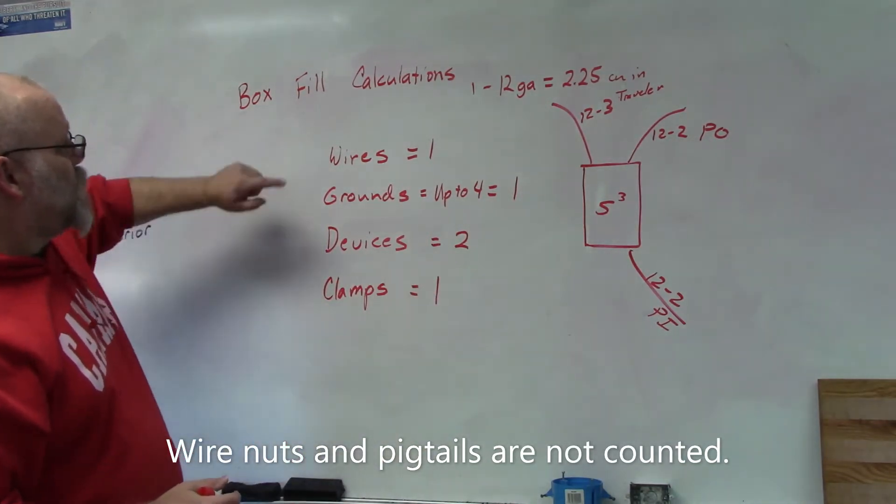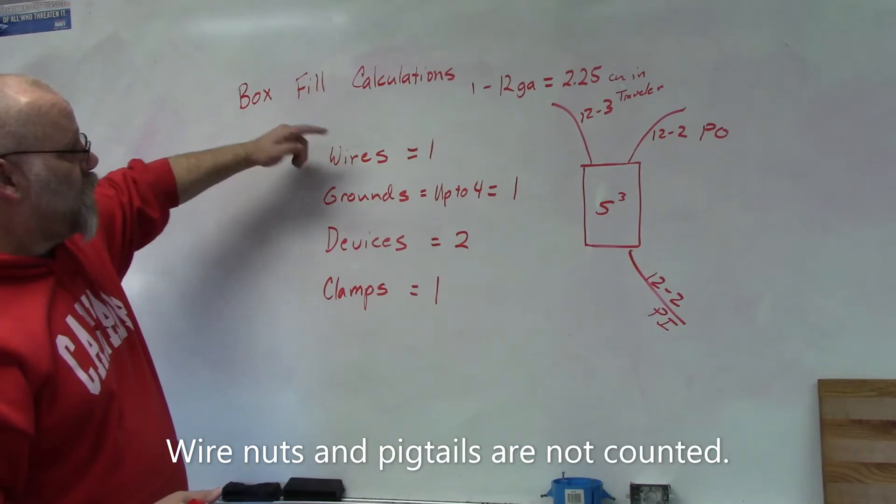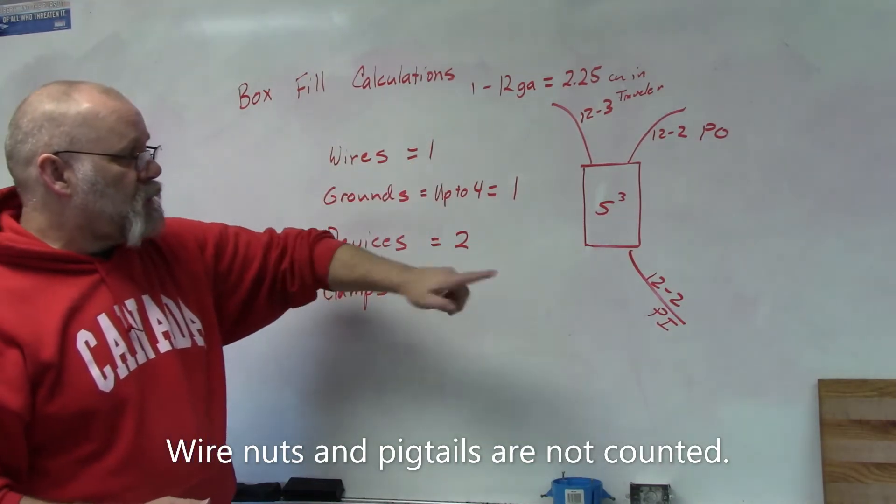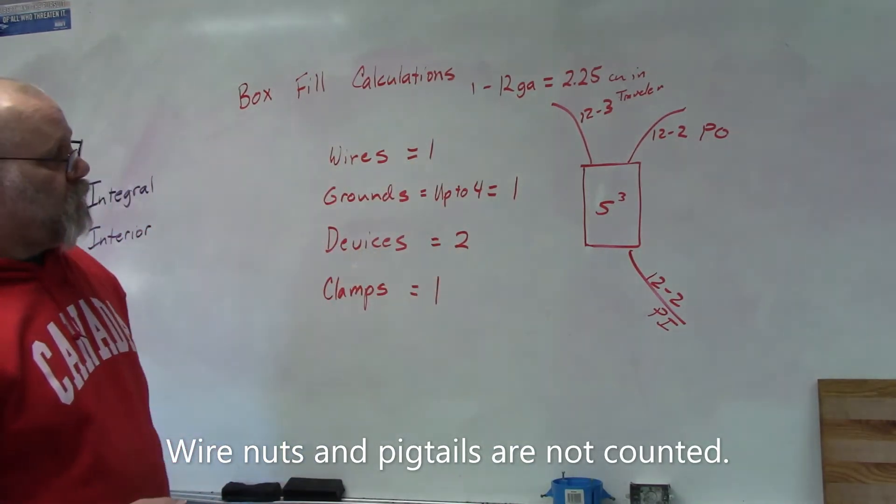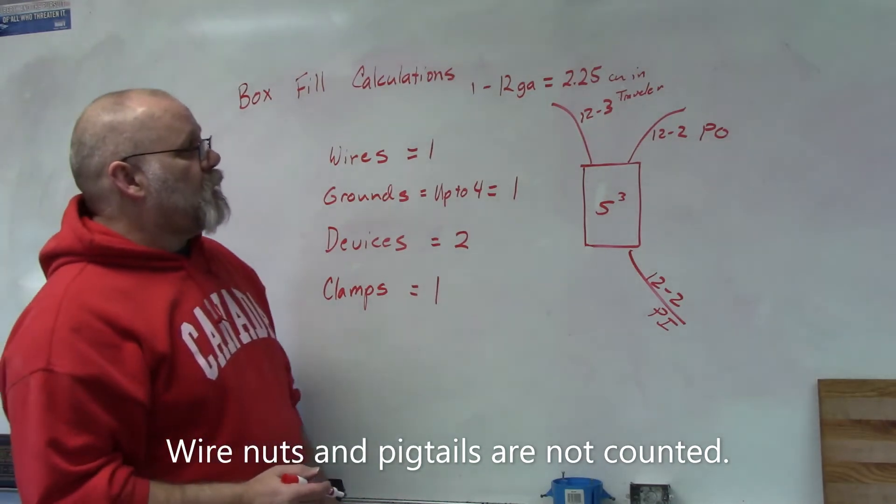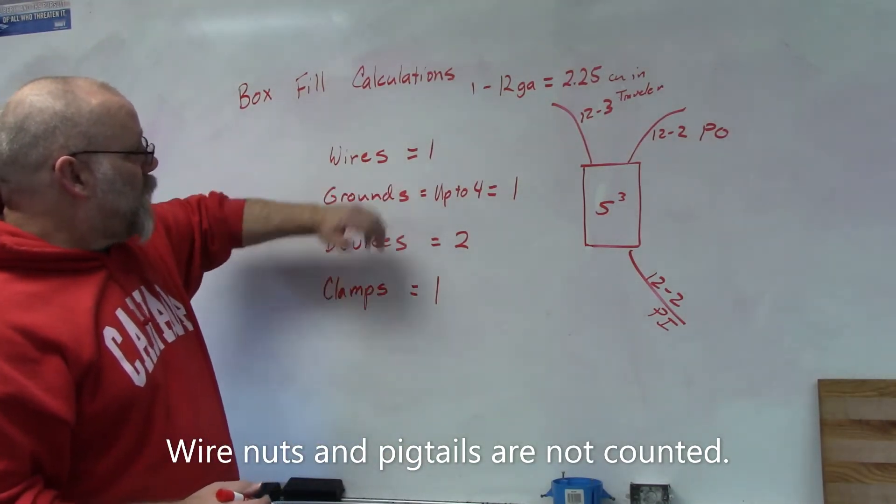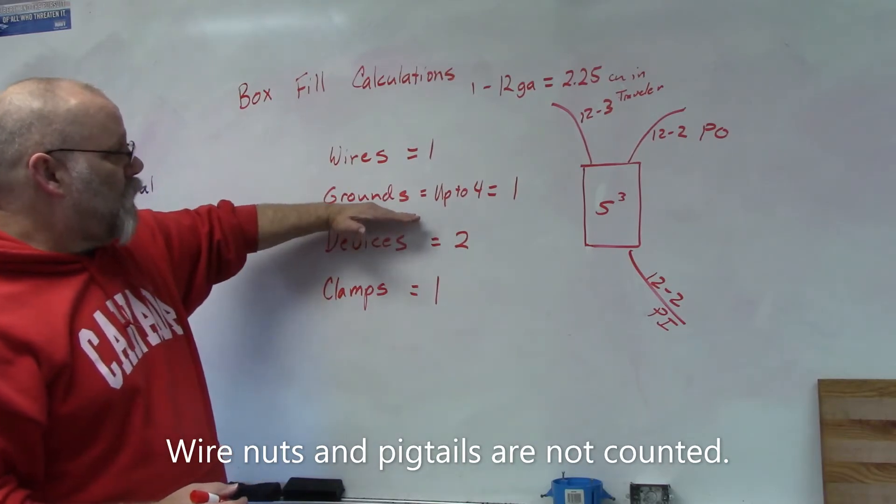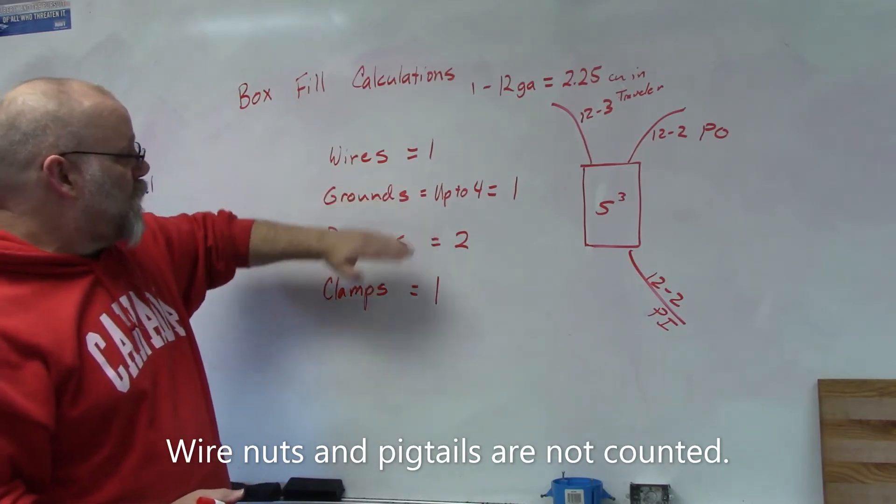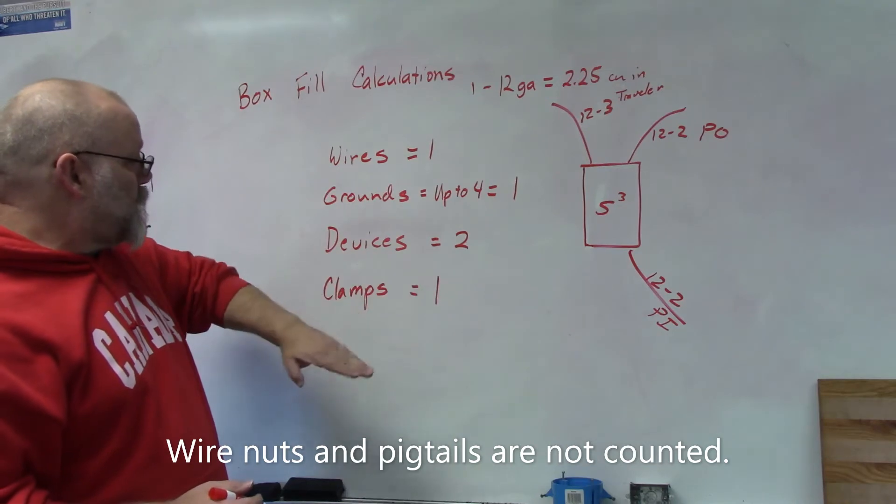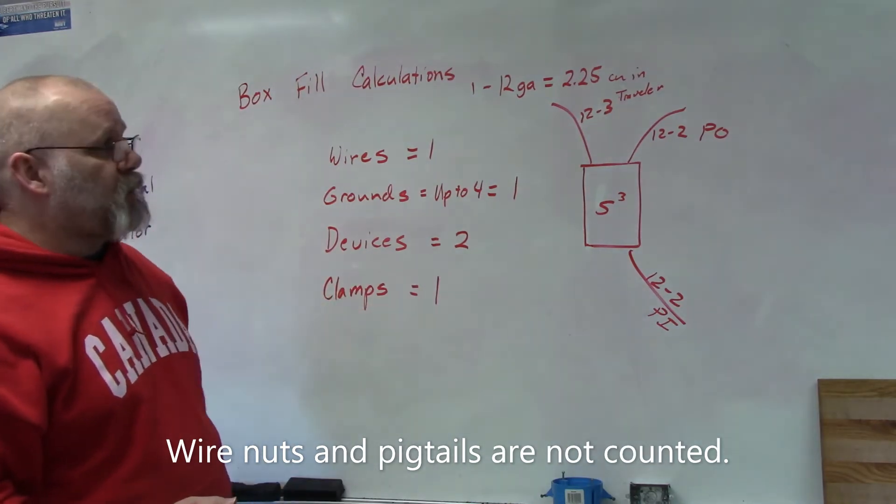So what we can do is either method. We can use the number method or we can use the cubic inch method. So the number method is you count one for each of your wires, you get one for up to four grounds, you get two for the device and one if it has any type of internal clamps.